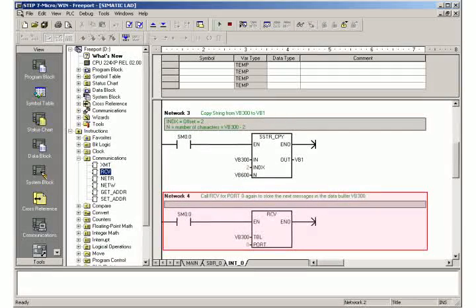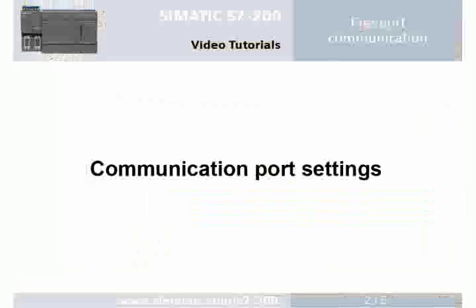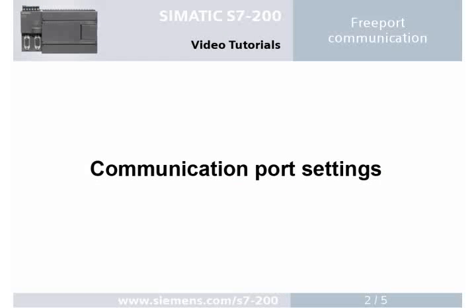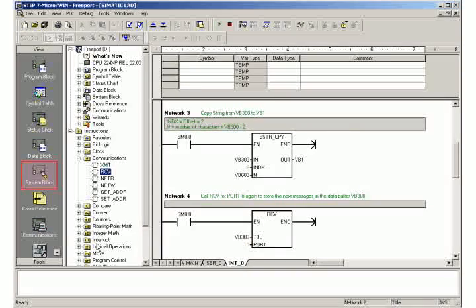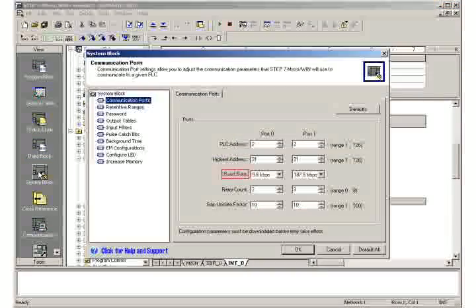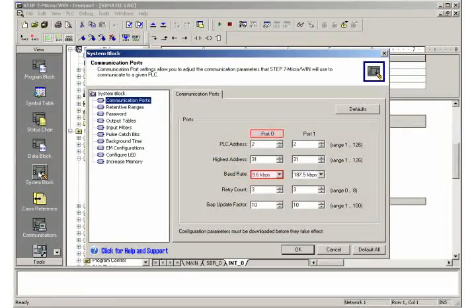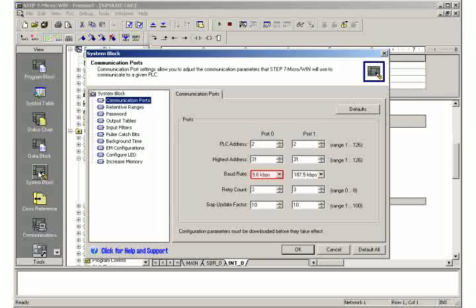In network 4, the communication block RCV must again be called in order to receive the next message. Step 2: Communication port settings. Go to the view of the system block. Set the baud rate of port 0 to 9.6 kilobit per second.